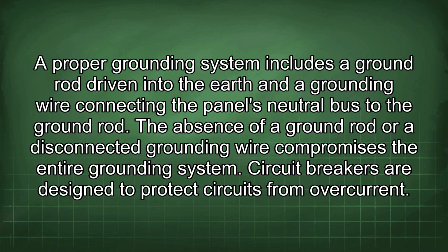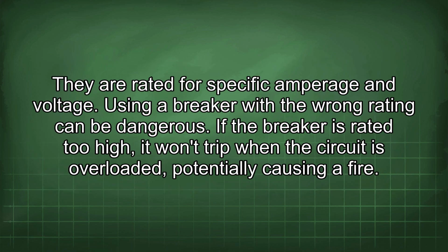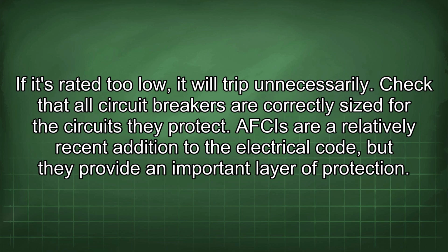Circuit breakers are designed to protect circuits from overcurrent. They are rated for specific amperage and voltage. Using a breaker with the wrong rating can be dangerous. If the breaker is rated too high, it won't trip when the circuit is overloaded, potentially causing a fire. If it's rated too low, it will trip unnecessarily. Check that all circuit breakers are correctly sized for the circuits they protect.